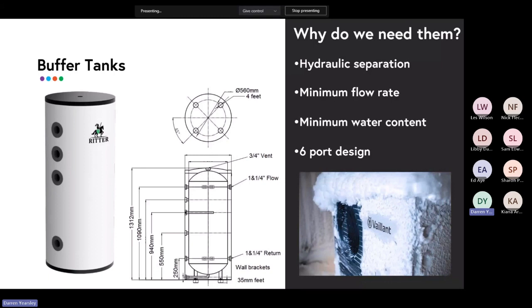So we have a break on the other side of the buffer where we use a very large plate heat exchanger with a very small temperature difference across it. So typically we've only got a 2 or 3 degree difference between the primary flow from the buffer and the secondary return going back to the storages. So if we've got 67 degree water in the buffer, we'll have 65 degree water going to the storage tanks. So we oversize the plate heat exchanger to allow us to operate in that way.